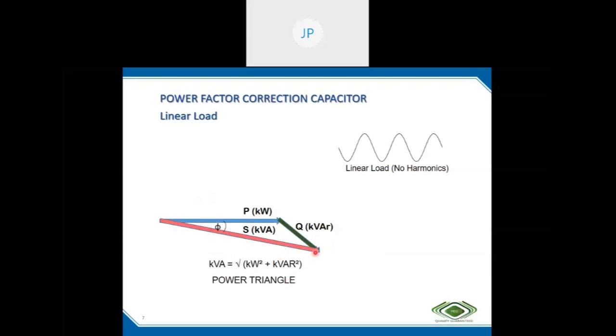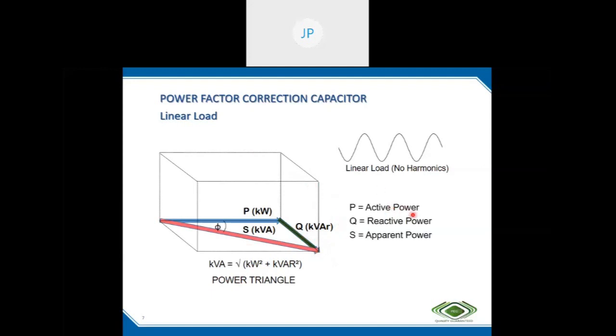Actually, this is true only for a right-angle triangle. But this is actually a right-angle triangle shown in three-dimensional view. This presentation is required to highlight how the harmonics affect it. P is active power, Q reactive power, S apparent power or total power. And power factor is by definition how much portion of the total power or apparent power is available for delivering active power. So S is the total power, the square root of P square plus Q square, and power factor is P by S.